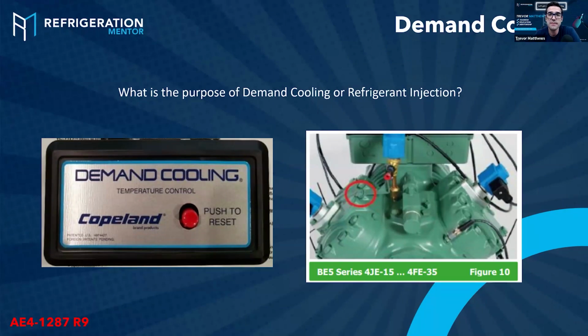That mass flow starts to slow down, so we're not getting enough cooling. Now that increases the temperature, so now that risks what? It risks our oil starting to lose lubrication and potentially starting to break down. This is why we see what Copeland calls their brand demand cooling, refrigerant injection. The other manufacturers, when you get onto a scroll, they call it EVI for Copeland. We'll dive into a lot of that stuff.